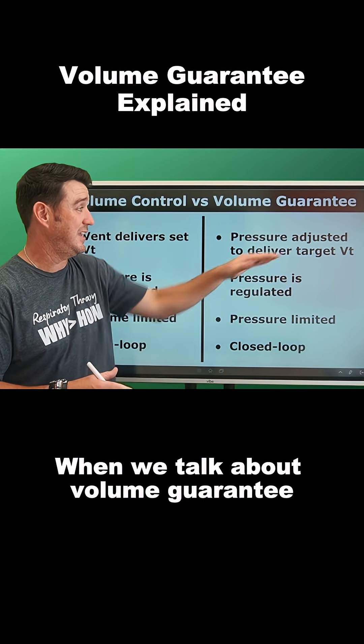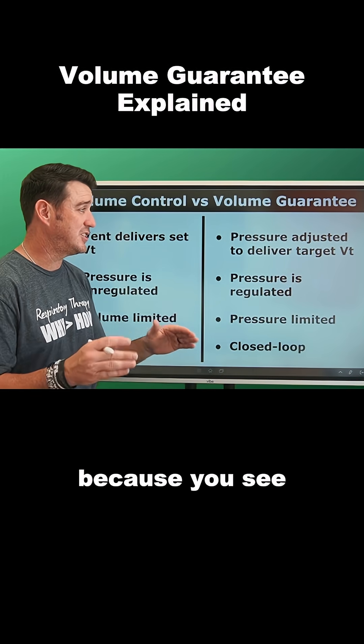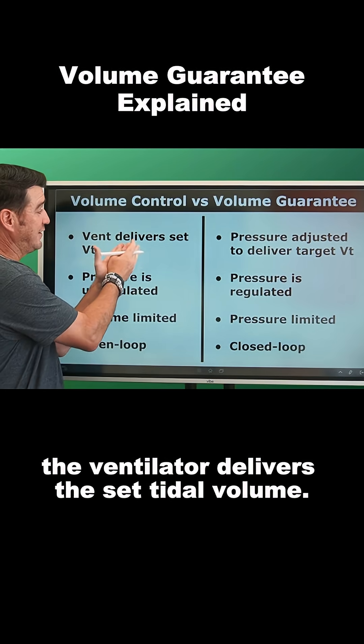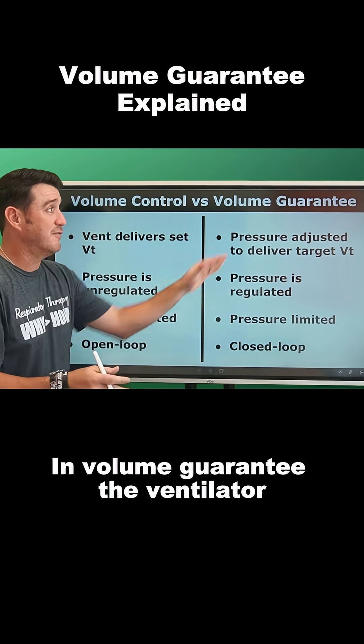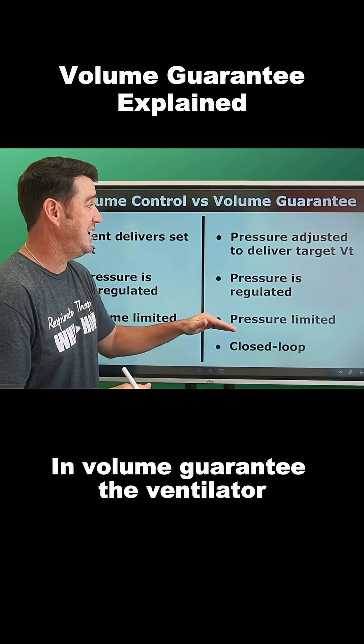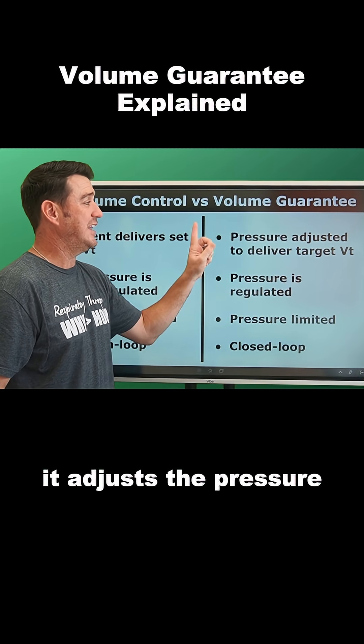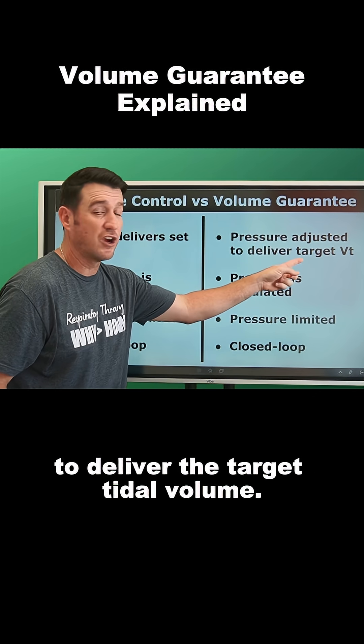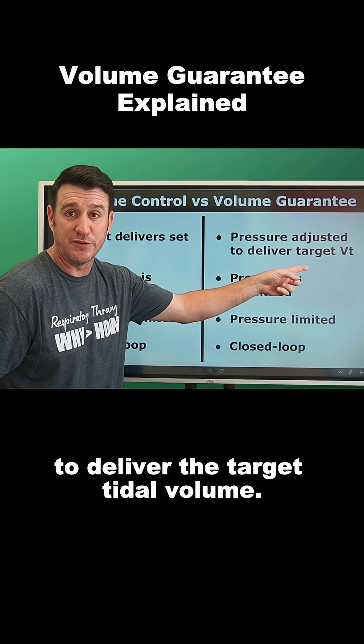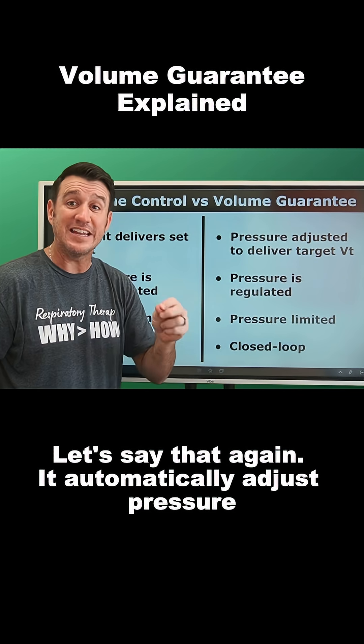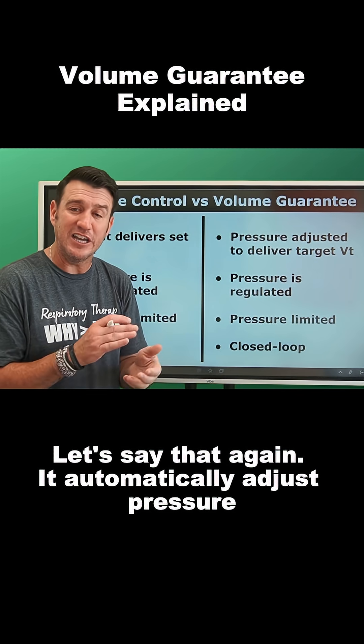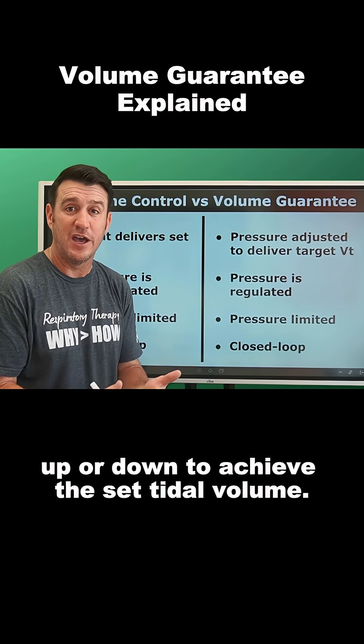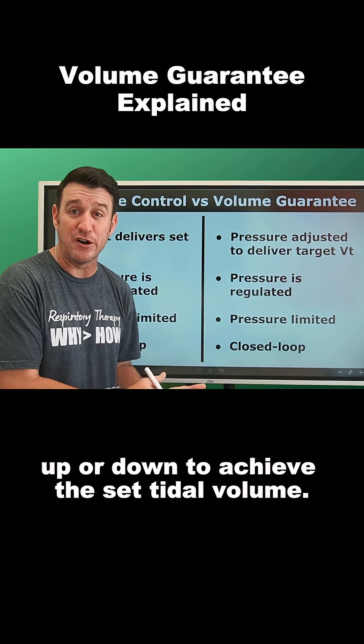When we talk about volume guarantee, the first thing we notice is in volume control, the ventilator delivers the set tidal volume. In volume guarantee, the ventilator adjusts the pressure to deliver the target tidal volume. It automatically adjusts pressure up or down to achieve the set tidal volume.